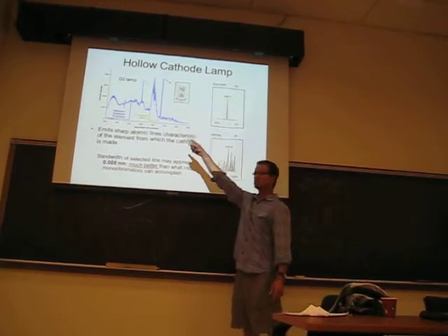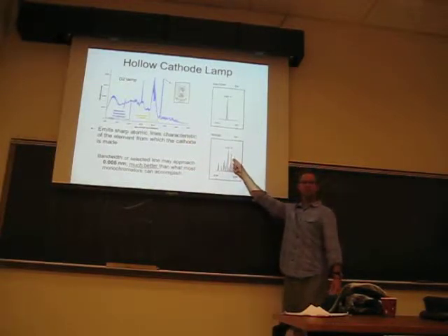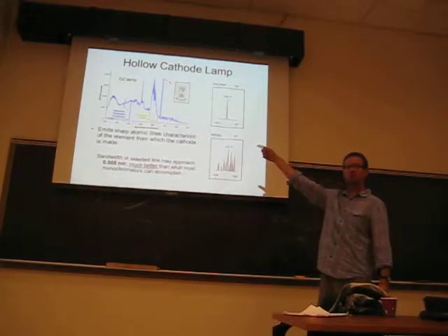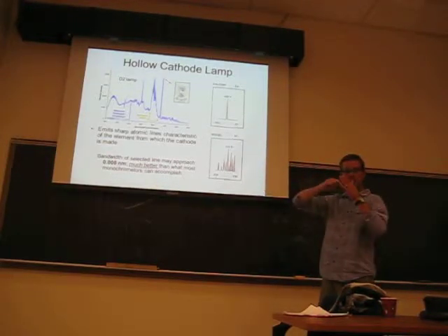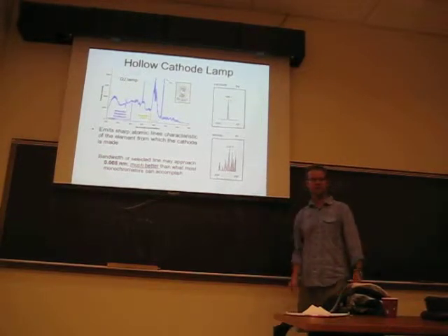These are really cheap, $50. These are like $300 to $400, $500. And you can get away with that in molecular absorption because the absorption bands are broad. But you can't get away with that in atomic absorption because the atomic absorption bands are very, very thin.